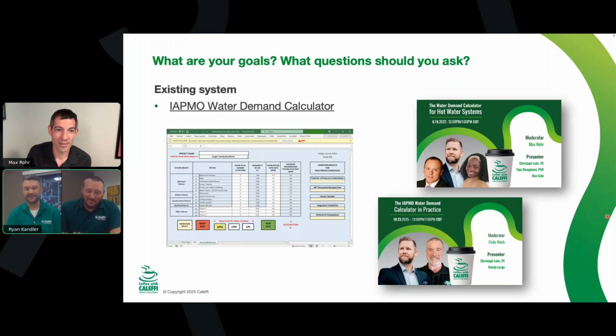Definitely the water demand calculator. Yeah, I mean, it's just so much more accurate. I've even seen case studies where you size it with the water demand calculator instead of Hunter's curve, and it's a drastic reduction, something like 70% reduction in flow. And then when you actually strap an ultrasonic flow meter on there and get some real world data, it's even below that. Even the water demand calculator is oversizing at that point.